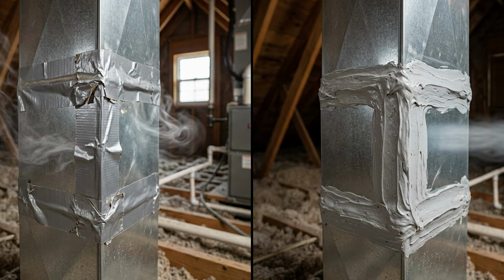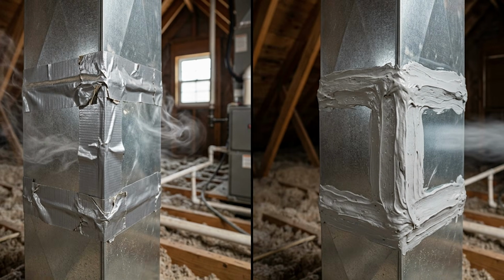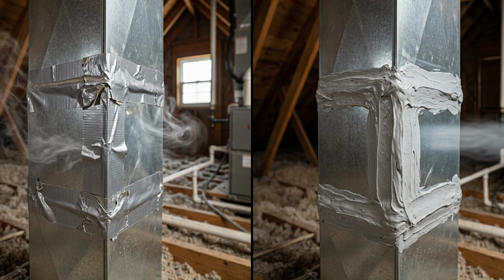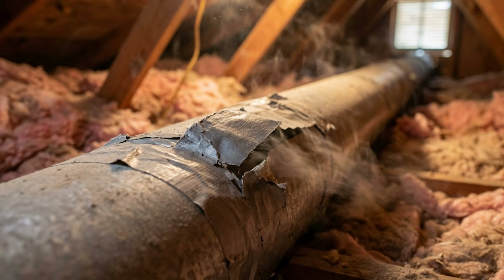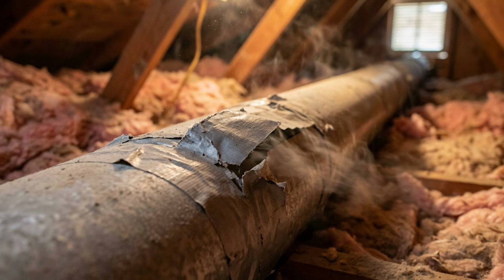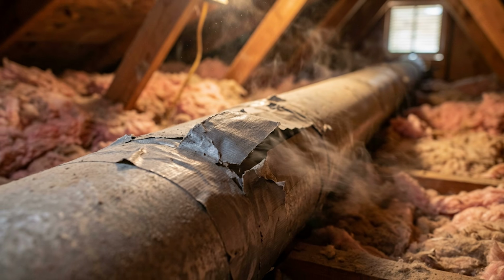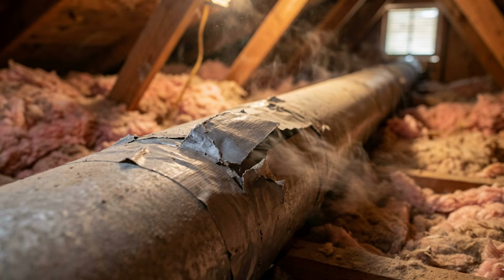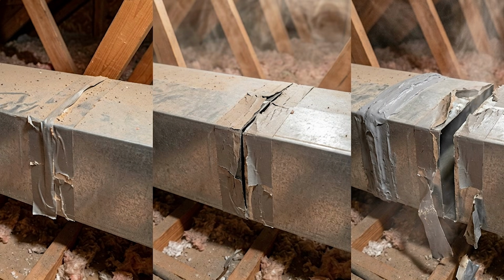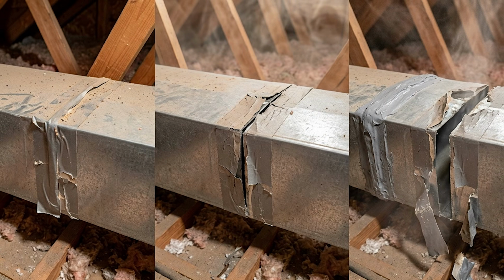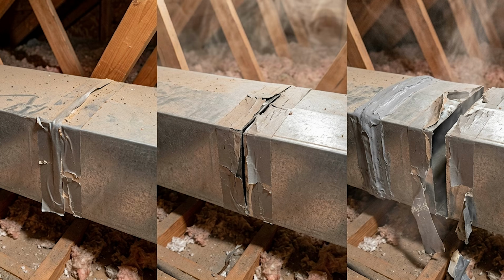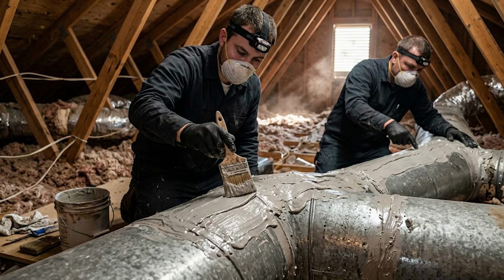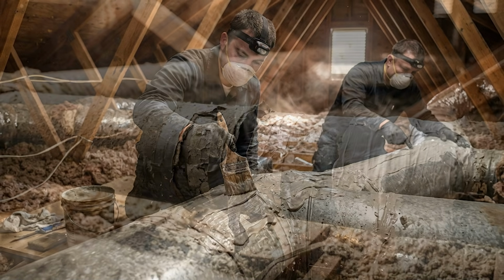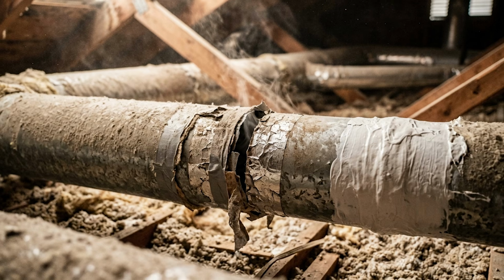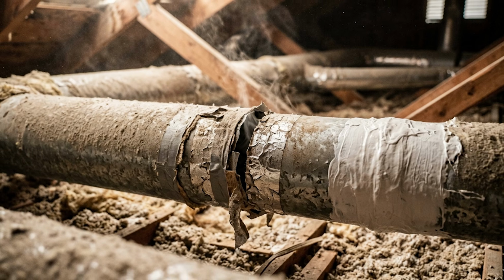This is the critical difference between mastic and duct tape, and I want to be very clear about this because it surprises almost everyone. Regular duct tape, despite having the word duct right in the name, does not work on ducts. The adhesive breaks down in the heat, it dries out, it falls off. Within 2 to 5 years, it is gone and the leak is back. This is not a theory, this is documented. This is why HVAC professionals use mastic, and it is why the joints someone sealed with duct tape 10 years ago are leaking again right now.